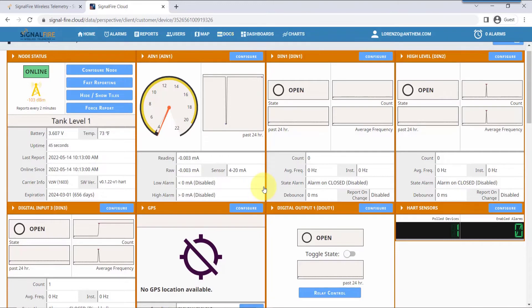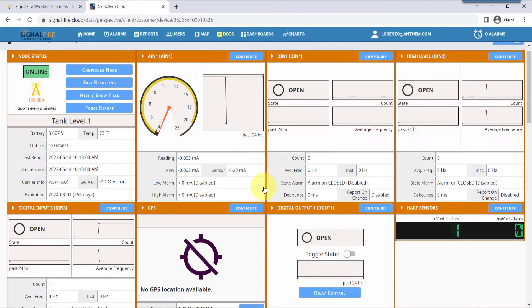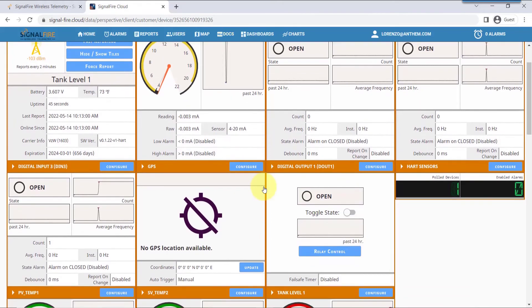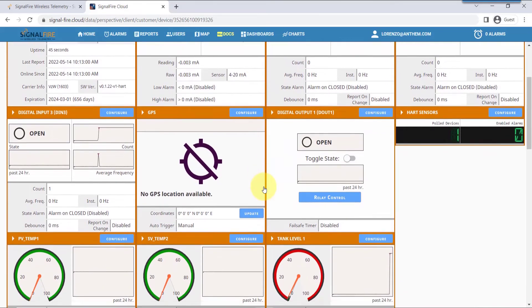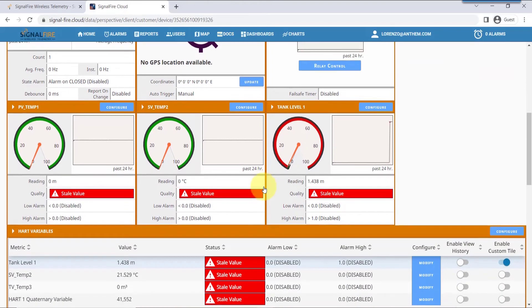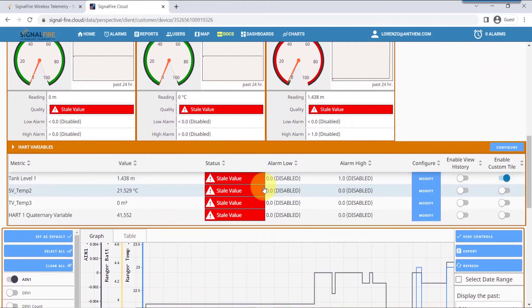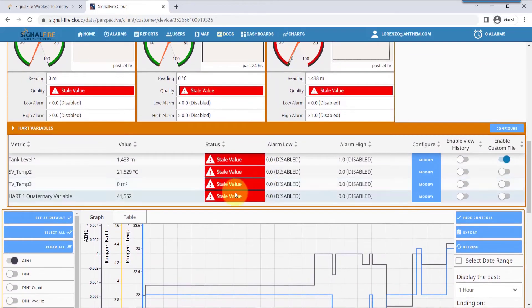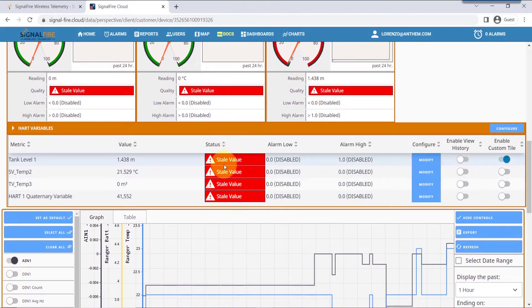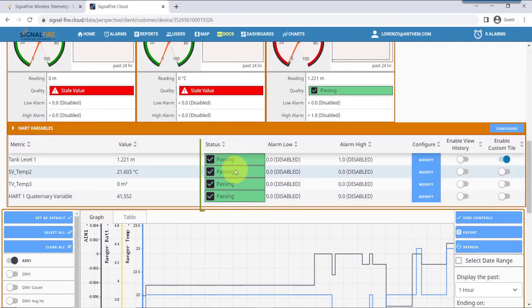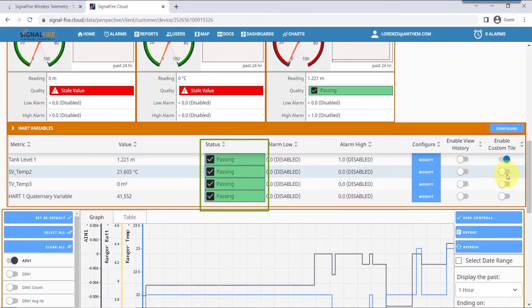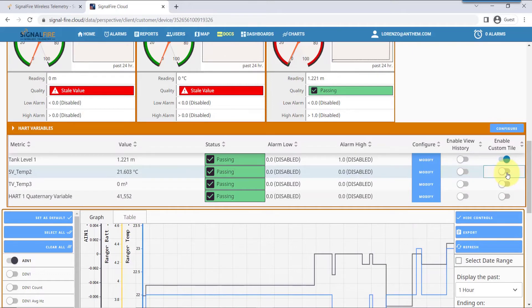Click Force Report and then wait for the duration that you set before, which is about 10 seconds, for the sensor to turn on, power, and then make the measurement. When the measurements have been done, you'll notice that the cloud will refresh and the values will now turn to green. This means that we have successfully powered the sensor and made the measurement from that HART device.